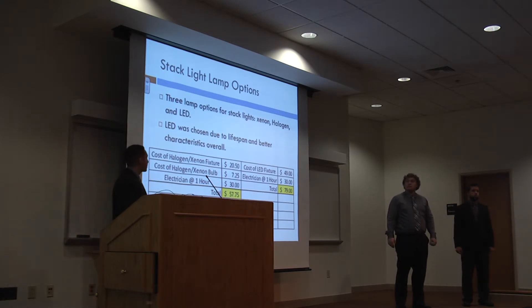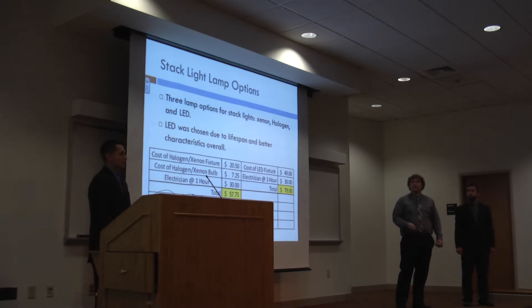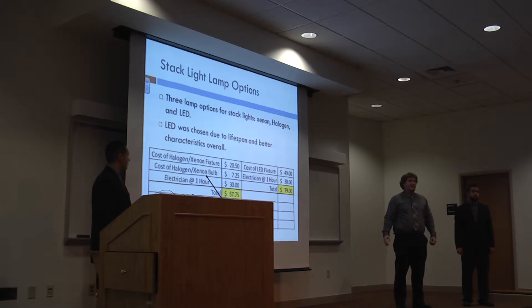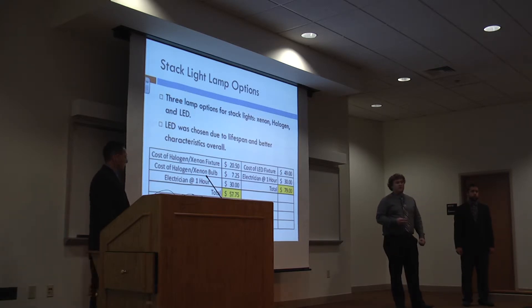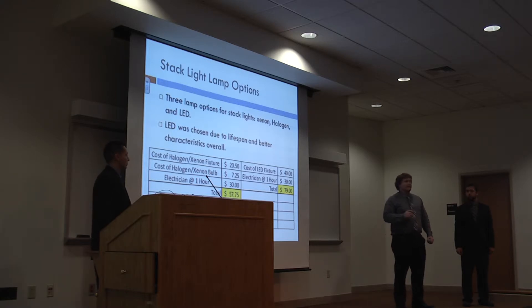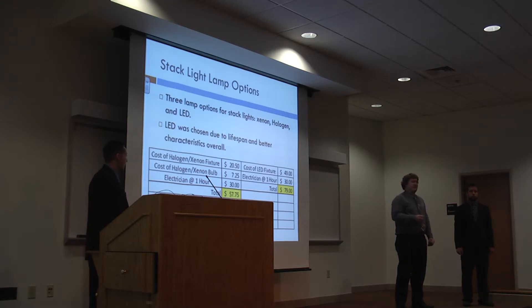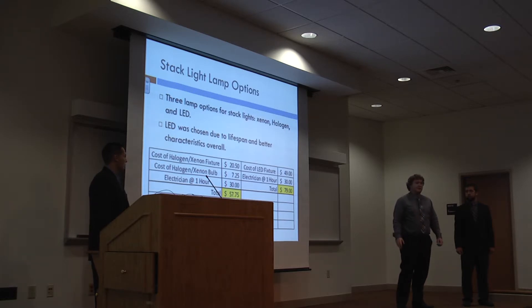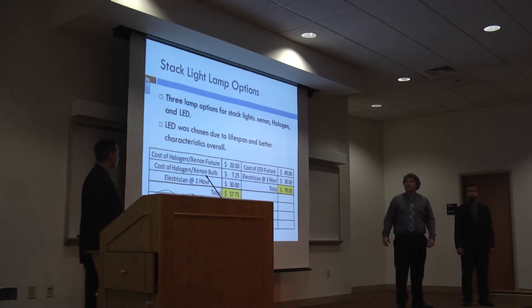For the stack light options, there were three main types: xenon bulb, halogen, and LED. The result we chose was the LED light. We did a cost analysis — if you had to replace a halogen or xenon bulb, which is rated at about 2,000 hours, versus the LED which should last 25,000 hours. If you just have to replace one bulb, there's your cost difference in choosing the LED over the two incandescents.